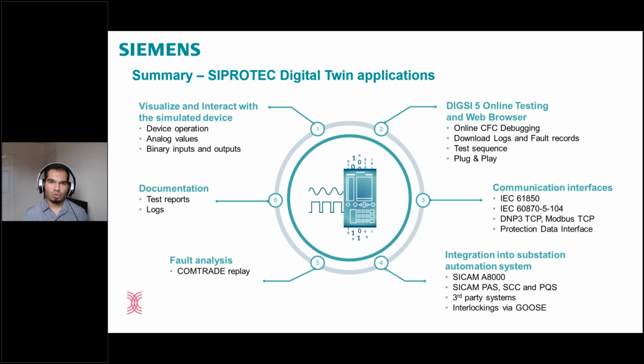Looking at point number two, you can do online testing in a web browser. So you make logics, and you want to validate whether those logics work right or not. So you're able to do online CFC debugging, and then if you want to have a proof that the logic works, you can download the logs or the fault records if it's a protection function. You can create test sequences and play them in the relay. It's similar to your Omicron state sequencer. So you create multiple sequences and you play them on the relay.